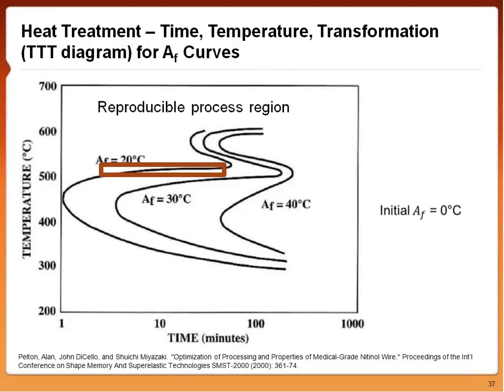So taking this point to operate on your TTT diagram to change your AF or shape set your material is not the best thing. You want to reach a region over here on a plateau where basically you're not going to see much of a difference between 8 minutes and 10 minutes in your processing time, and you're going to get that AF temperature that you want. So this part of the curve is more stable to your processing. What it produces is more repeatability in your processes and in your devices.